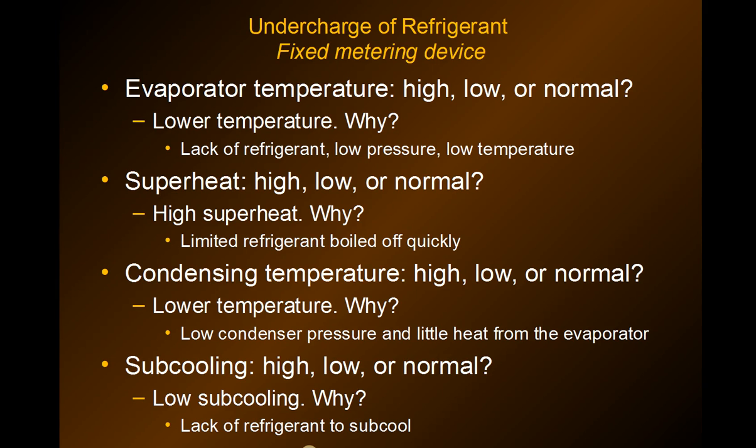These systems are critically charged — they only have ounces of refrigerant, a pound or so. When a cap tube system loses 10% of its rated refrigerant charge, system performance starts to degrade. That doesn't take many times of hooking up your gauges with long hoses before you've removed enough refrigerant from this critically charged system to affect its operation. If you suspect that may be the case, don't start troubleshooting yet or you're going to chase your tail.